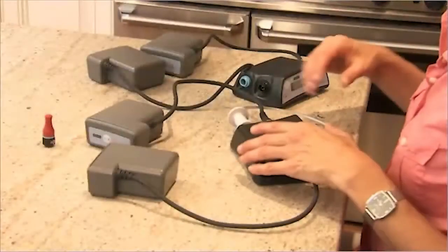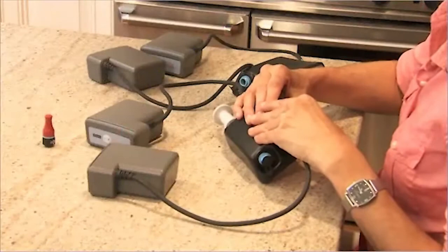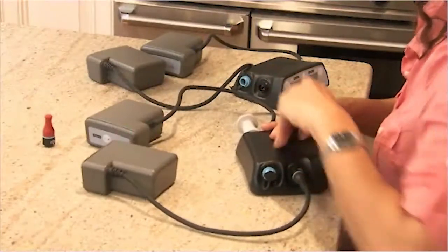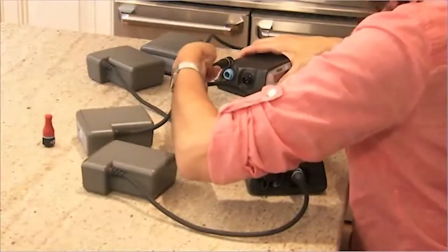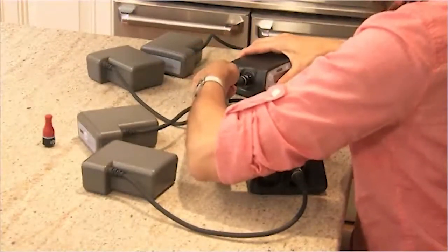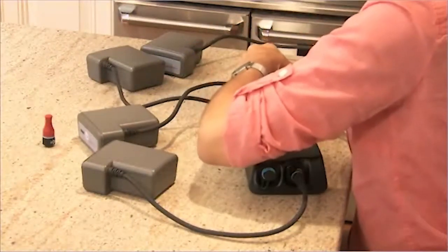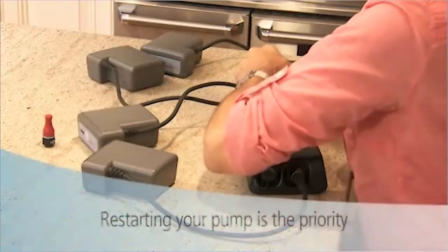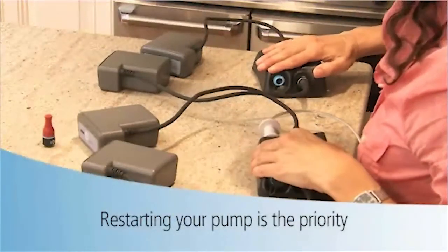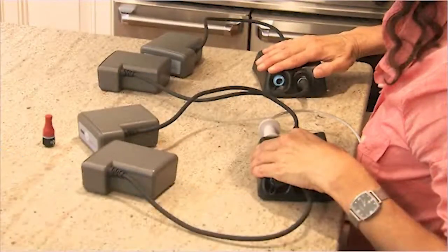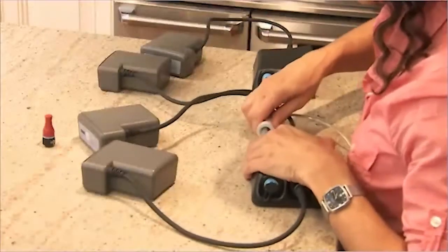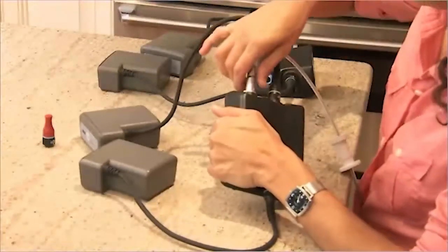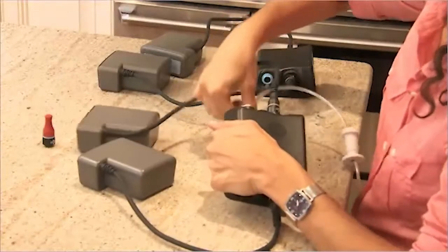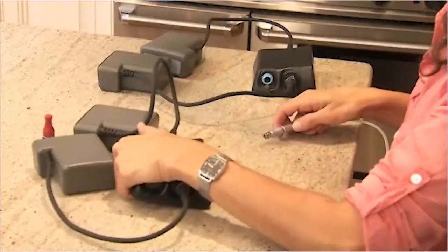If a controller needs to be changed, follow these steps as demonstrated by the patient. Connect power to the new controller. Please note that a VAD stopped alarm will start, but it will end once the pump drive line is connected. Restarting the pump is the priority, so don't worry about silencing the alarm until after getting the pump restarted. Next, pull back the white driveline cover on the driveline to expose the silver connector. Disconnect the driveline from the original controller by pulling the silver connector away from the controller.